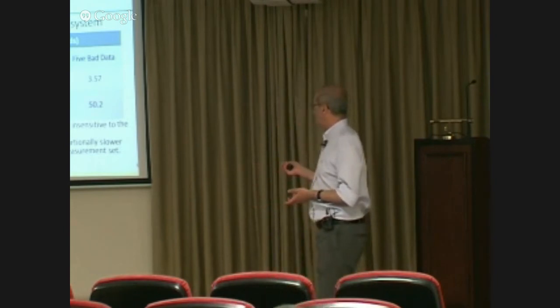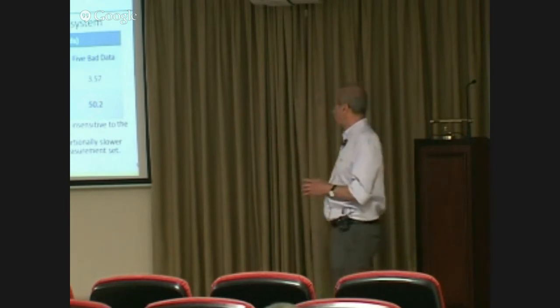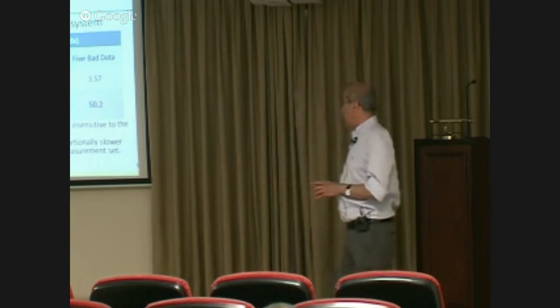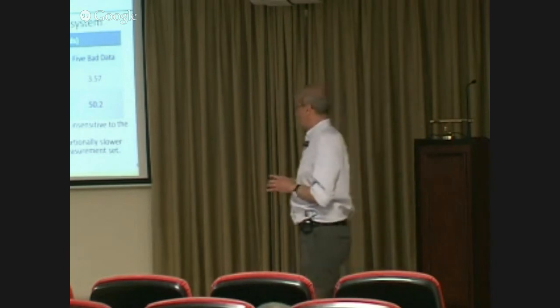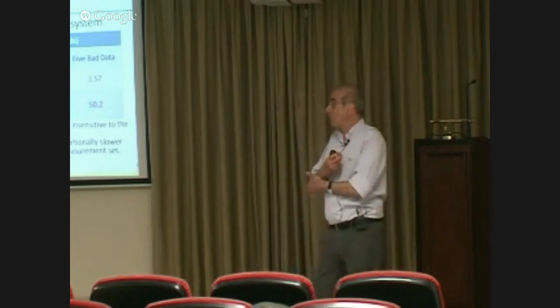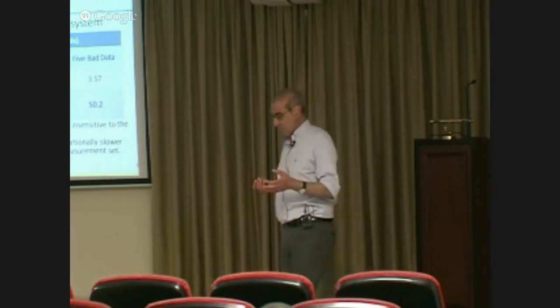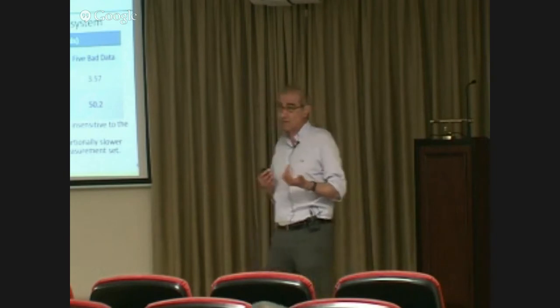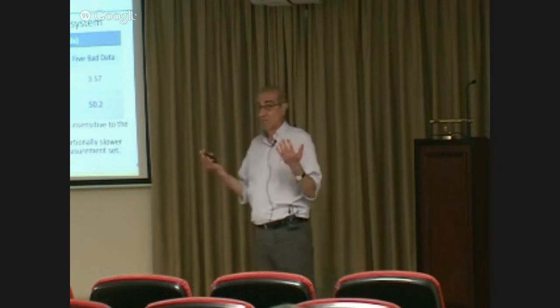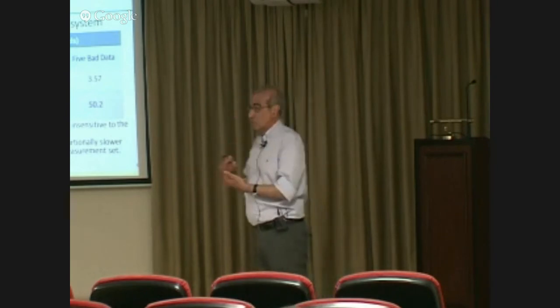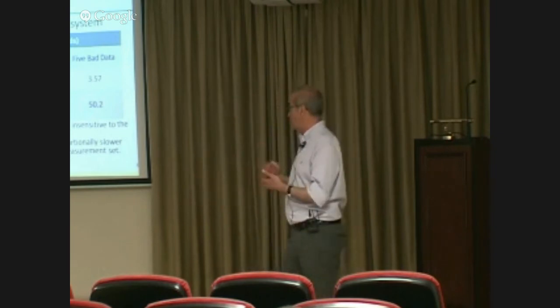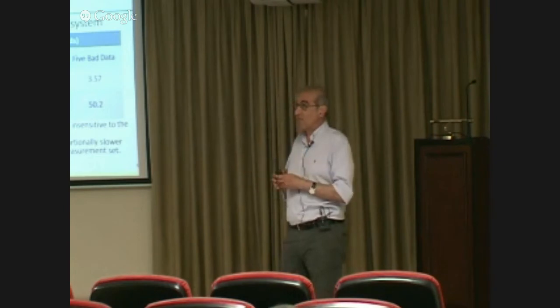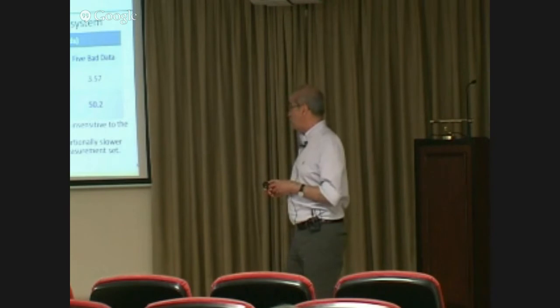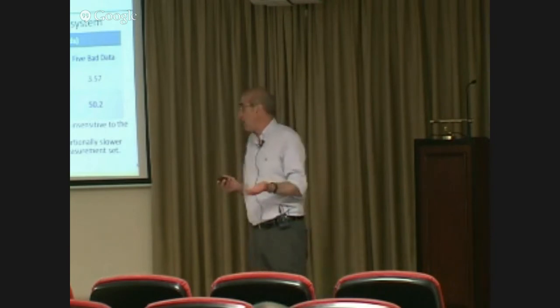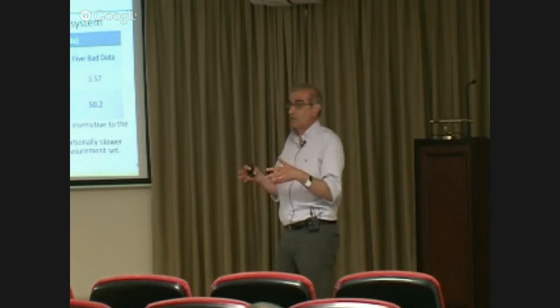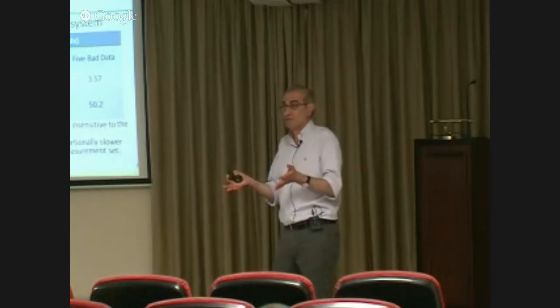You can see it increases almost linearly with the number of bad data because it's a cyclic process. We didn't test other techniques like reweighted least squares because those are more meaningful for SCADA or nonlinear problems, since the nonlinear solution is itself iterative. During those iterations you can reweight everything, but here the problem is linear, so you can get the solution in one shot using WLS. If you use reweighting, you turn the weighted least squares problem into an iterative one.